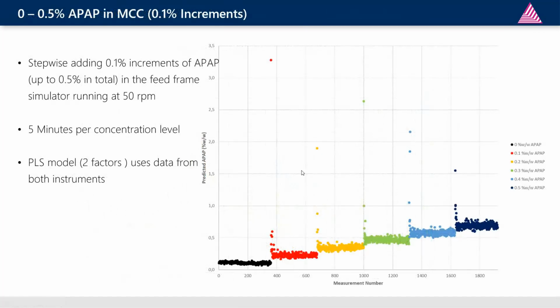And we challenge this developed method with a very low concentration of APAP in MCC. The calibration itself was built on a large range from 0 to 10%. And then on day 2, we were challenging the instruments with stepwise increments of 0.1% APAP up to 0.5% in total. So actually we're looking at how we can deal with low dose. Each concentration level was operated for about 5 minutes. The PLS model used had 2 factors because it was using data from both instruments. So at least one factor was also required to compensate for the variation between these instruments.